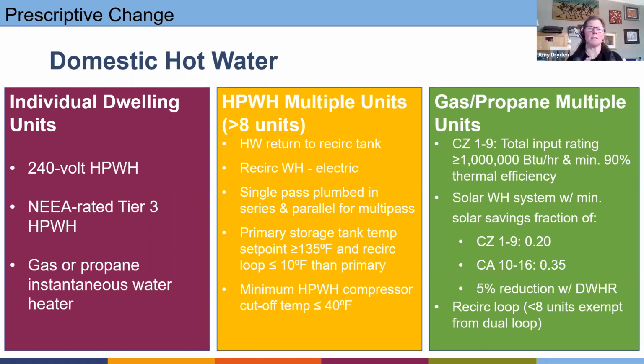And there are some requirements here in terms of single pass and multi-pass, based on the operation. Single pass goes once through the system, so we want that plumbed in series, as we're looking at the tanks, and then out to the building. Multi-pass goes through multiple times, and you'll see variance in that temperature differential, and those are plumbed in parallel. So there are some requirements in there. We'll go into more of these in detail in the multifamily training.